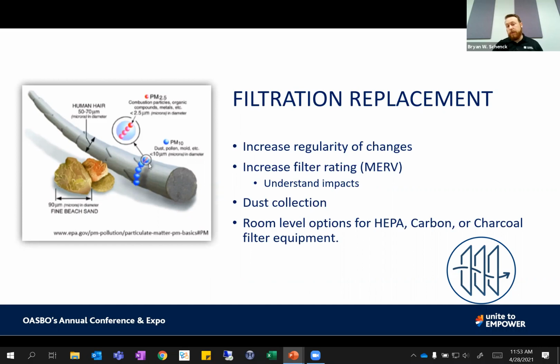And the higher you go on a MERV filter, the smaller the particulate that it filters out. Once you get past the MERV ratings, the highest of which is 16, you get to different types of filters like HEPA and carbon and charcoal, which get down to even smaller particulates. So the concern there is that your air handling equipment would have been designed for the MERV rated filters that are in them, and they probably won't perform very well with HEPA filters in there, or they would require additional maintenance. So that needs to be evaluated on a deeper level, certainly, to make sure that's the right decision to make within the mechanical equipment.